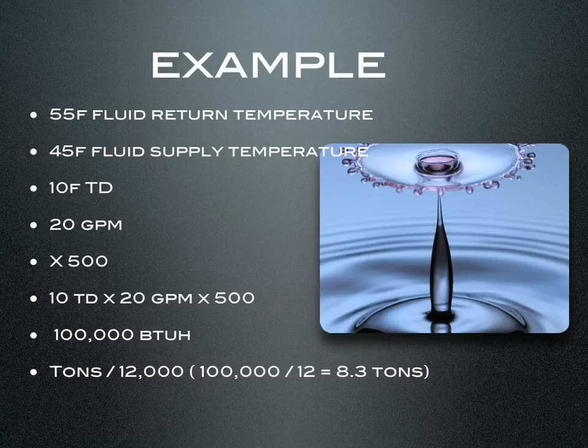One thing to keep in mind is every process is different. Processes are going to have different temperature differences, different supply temperatures, different gallons per minute. As long as you can take your temperature difference between the entering and leaving water temperature and multiply by gallons per minute, then times it by 500, you'll always come up with your BTUH.